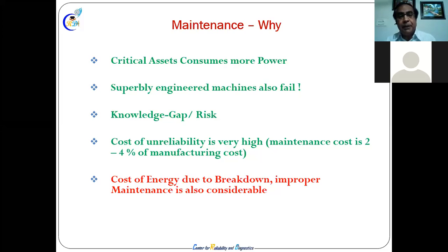Power consumption should be less, because critical assets consume more power. We have seen fans of 7 megawatt, 10 megawatt, just an ID fan. Can you imagine? Steel plant fans and all. So what will the power consumption be if maintenance is not there? It will be increasing. Alignment, machine alignment, unbalance, all these things will increase the power consumption. Such a machine's power consumption is very, very high. Cost of unreliability is very high.